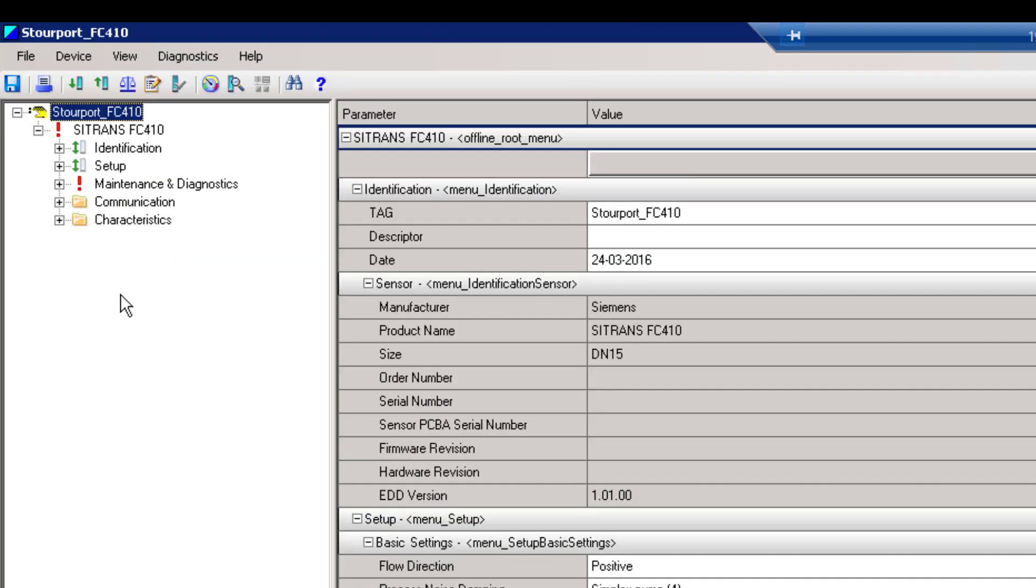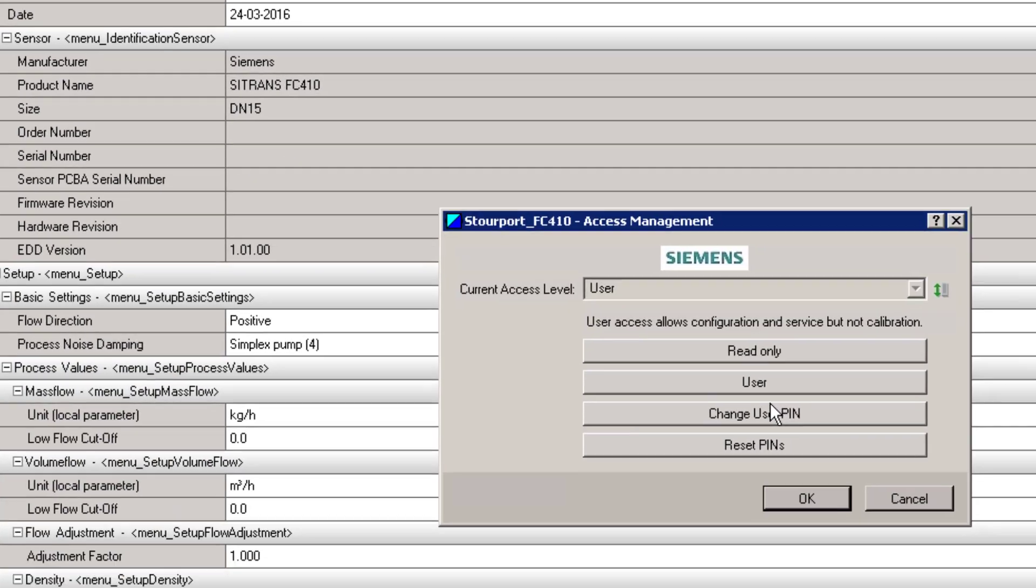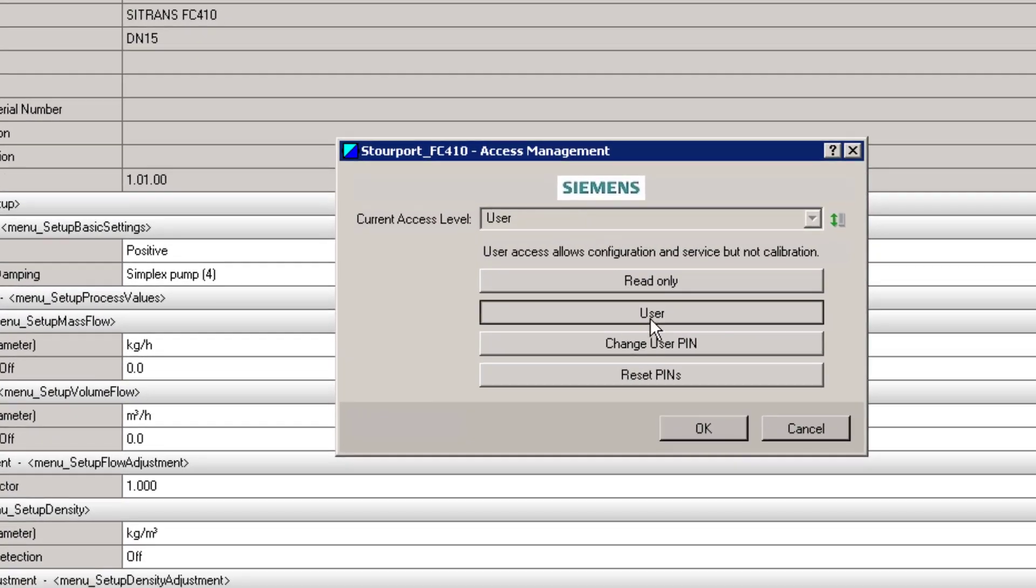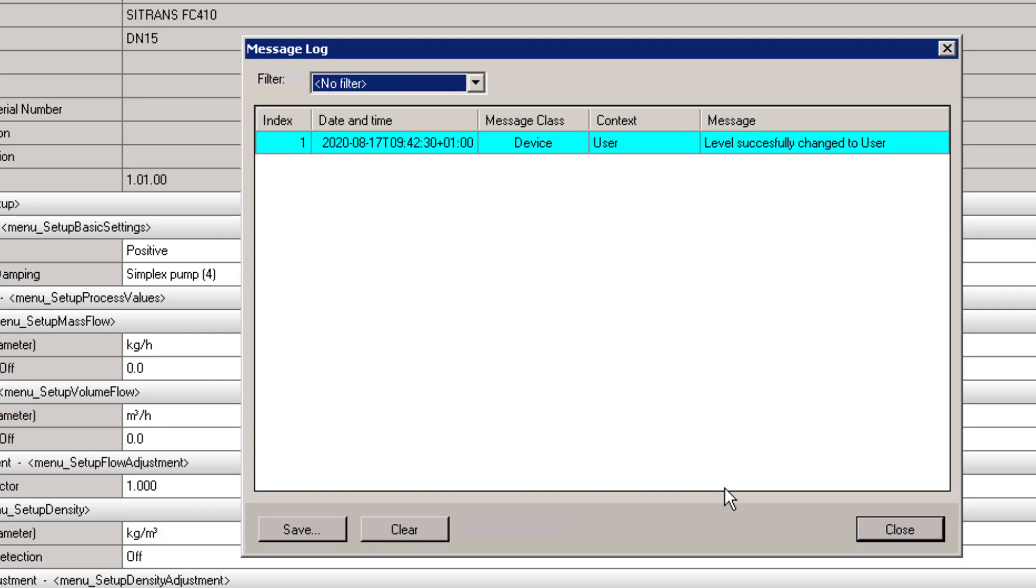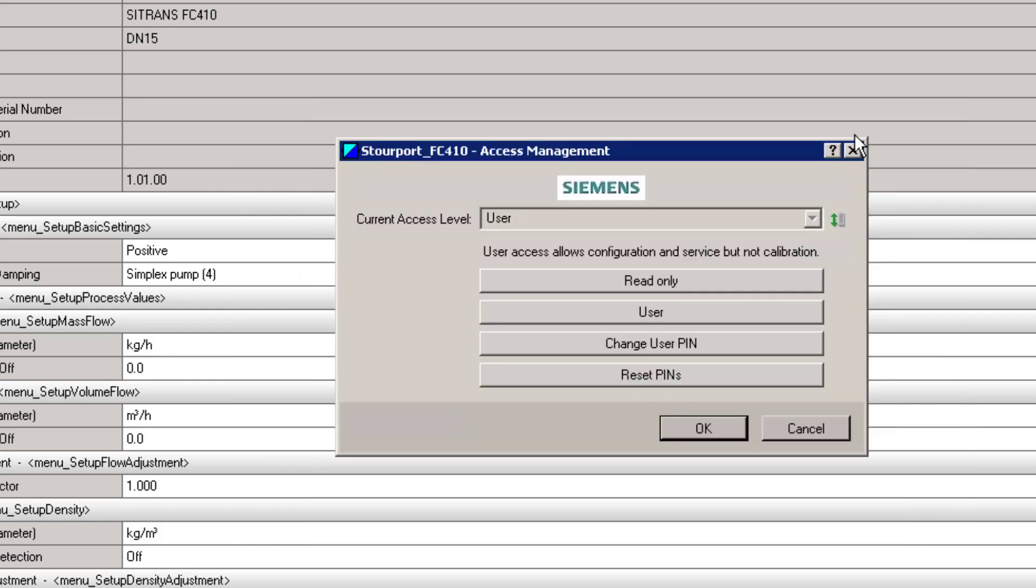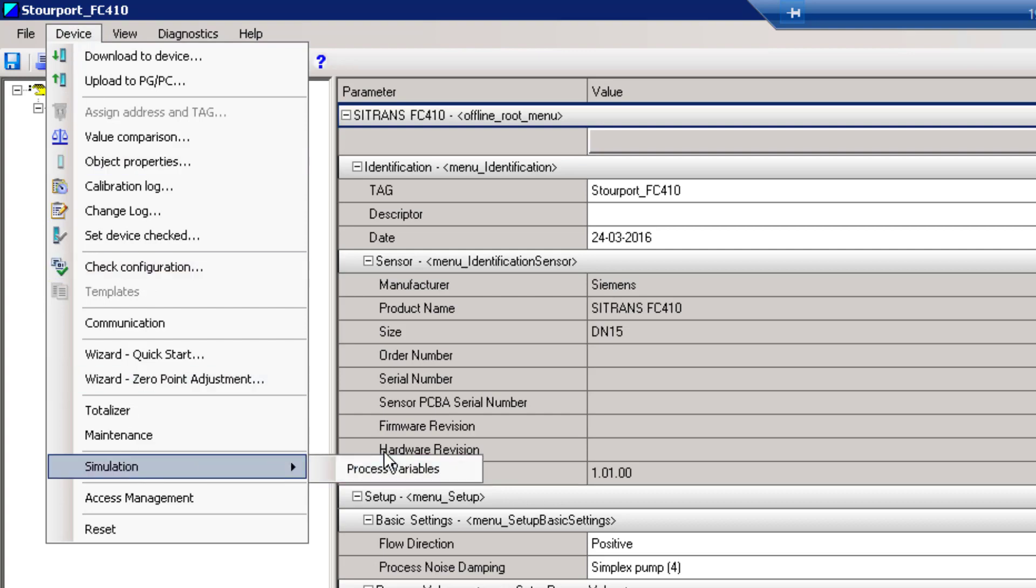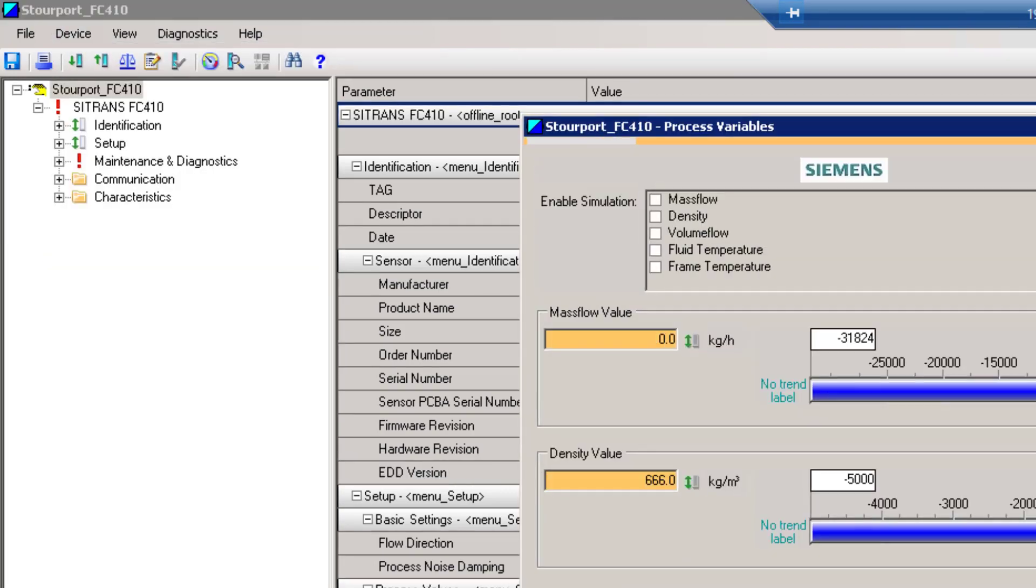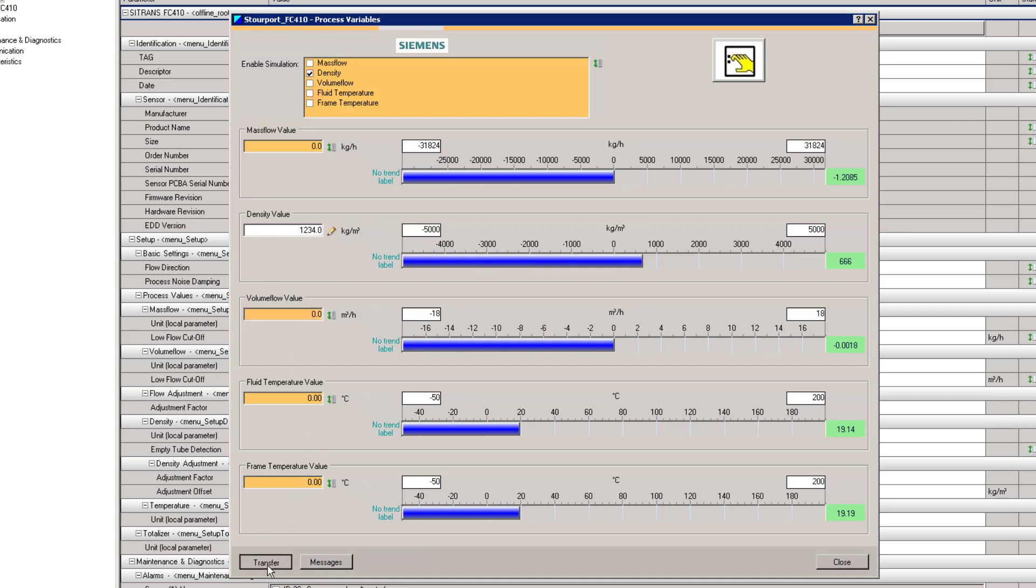So we will open this project and when we are in here the first thing we have got to do is to set the password. So go to access management, user will suffice and the password is 2457. When we have changed we can go to simulation and here we can simulate the process values. You can see here I have already simulated the density. If I want to change that to something else I can just enter that and then click transfer. And there is my value being simulated. So when we do the Modbus TCP connection with TIA Portal we should see that density value coming through.